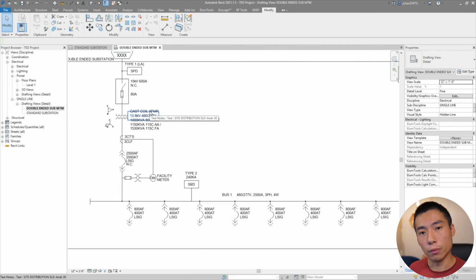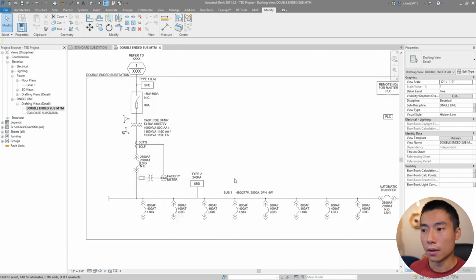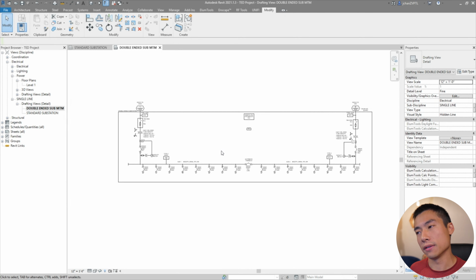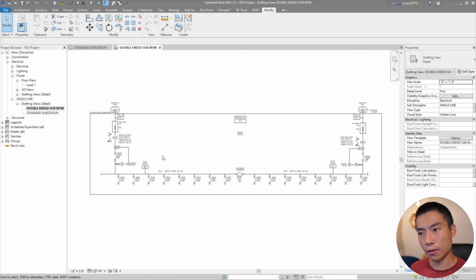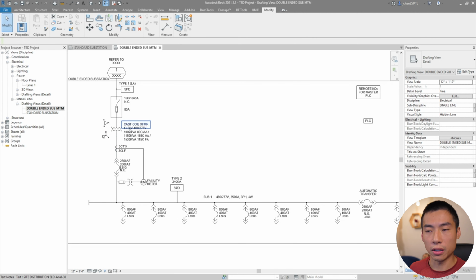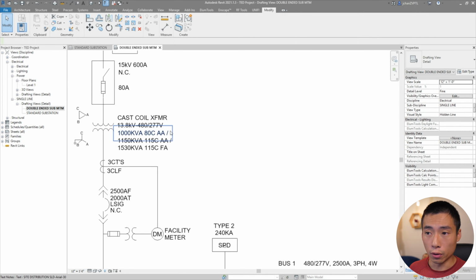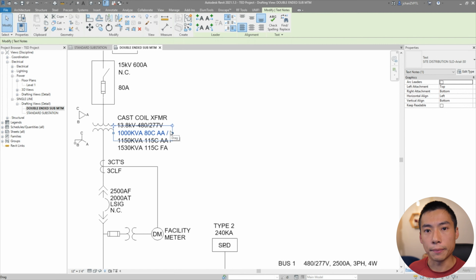So it's not a fully redundant substation. You'll have to shed some of your load in order to do that. So for reliability purposes, generally people like to size it so that under normal operating conditions, when your tie is open, each side is running at 50% capacity or less of your AA ambient air rating.